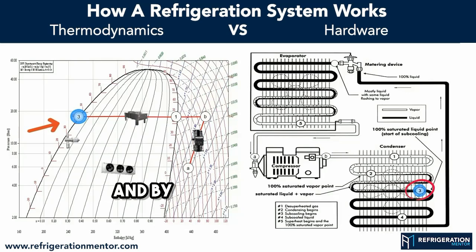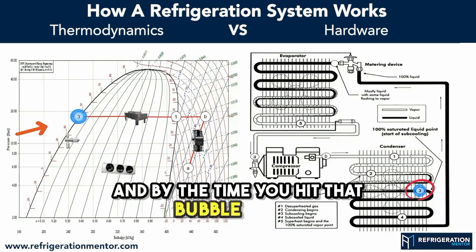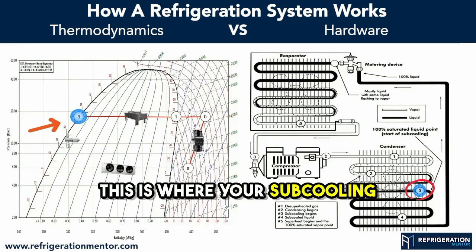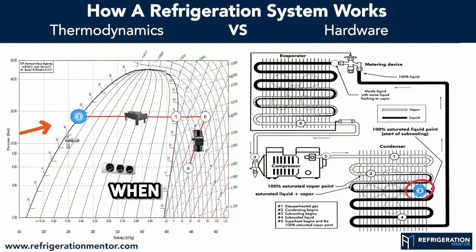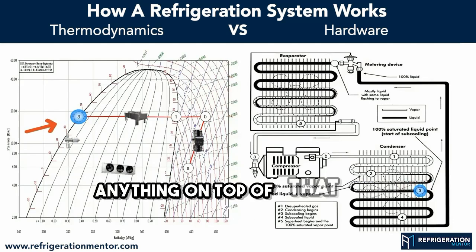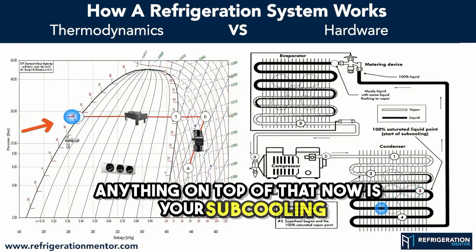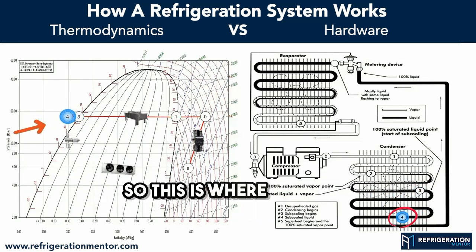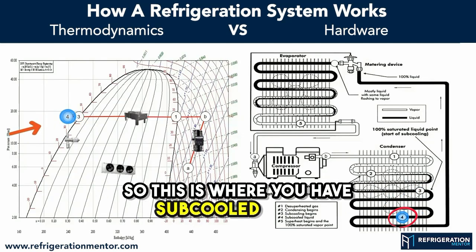And by the time you hit that bubble point, this is where your subcooling begins — when you have a full column of liquid. Anything on top of that now is your subcooling, so this is where you have subcooled liquid.